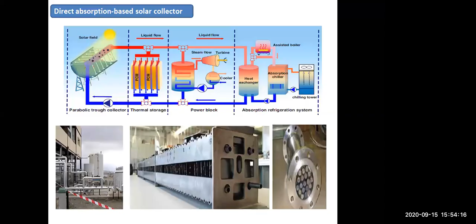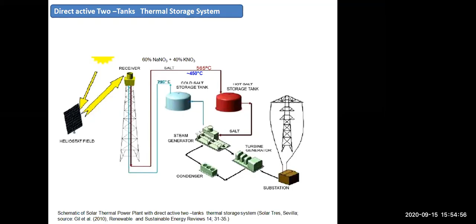Hot and cold fluids are stored separately, with no additional heat exchanger needed, allowing fast heat transfer. The freezing point of the salt is 120 to 220 degrees Celsius, so an auxiliary heater is required to maintain the temperature above freezing during night time.